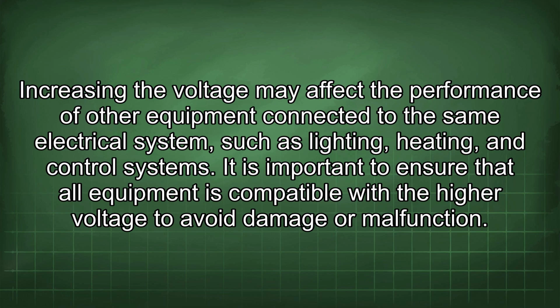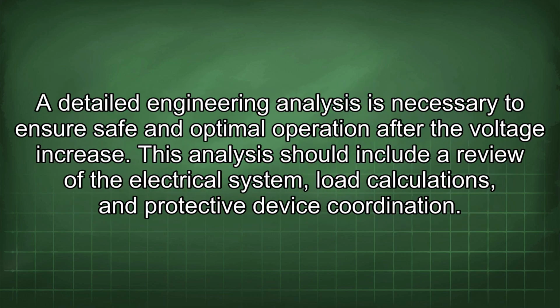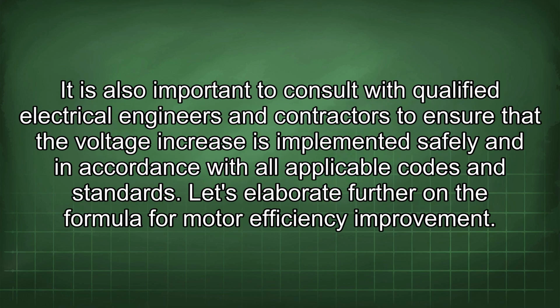It is important to ensure that all equipment is compatible with the higher voltage to avoid damage or malfunction. A detailed engineering analysis is necessary to ensure safe and optimal operation after the voltage increase. This analysis should include a review of the electrical system, load calculations, and protective device coordination. It is also important to consult with qualified electrical engineers and contractors to ensure that the voltage increase is implemented safely and in accordance with all applicable codes and standards.